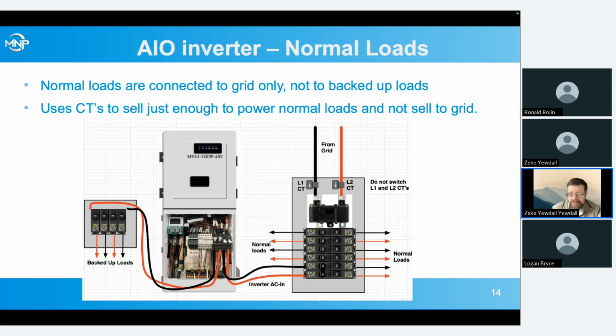What it does is we've got CTs on those two lines coming in from the grid, and the inverter can tell how much current is on those lines coming in from the grid. And what it does is it sells just enough power through its AC out to the backfed breaker in that main panel, to zero out the power used by all those other loads. So it's selling just enough power that there's no power coming in from the grid or going out. And that's what we call support normal loads. So even those loads, they're directly connected to the grid, but they're not drawing power from the grid because we're selling just enough to balance that out.